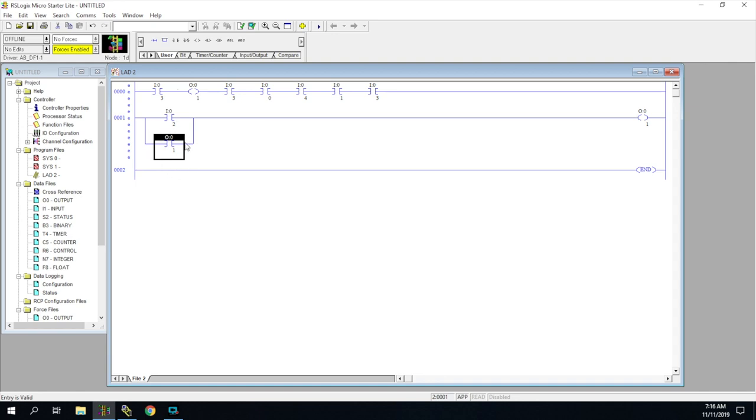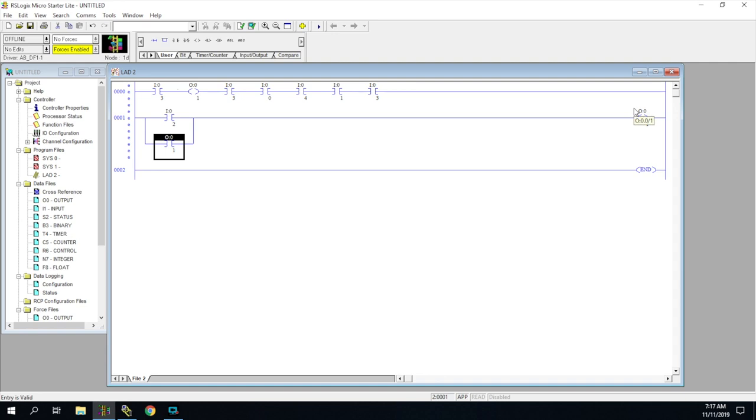The problem with this circuit is that it would not be able to be turned off in any way. We'd actually have to add a stop button in here. But we're going to get more into that ability when we get to kind of our little motor control section. But there's a reason you don't want to be doing this too. That is because there's no physical safeties on it. There's nothing that can tell the PLC that that motor's not running anymore, that output's not running. So let's say this was a motor control, and it did get burned up. Well, as far as the PLC is concerned, it's still running just fine. We need some feedback. So technically we'd probably use an auxiliary output or input for this rather than just a copy of itself.